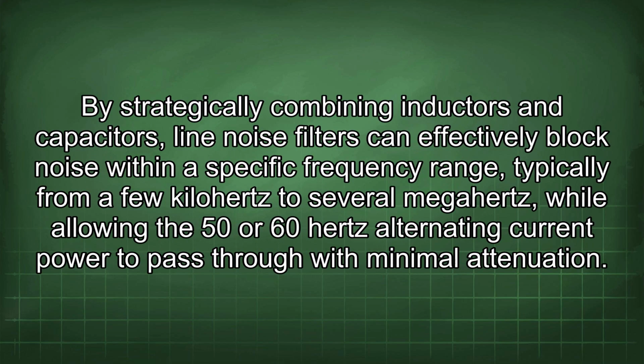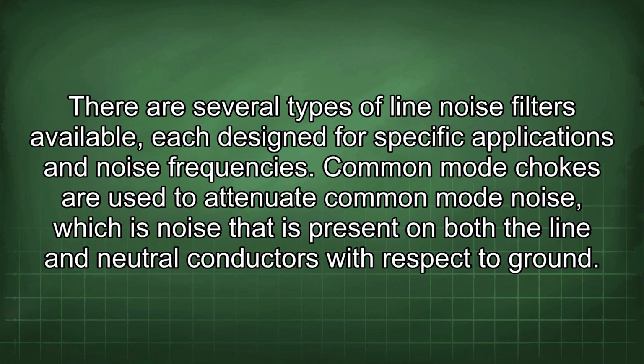By strategically combining inductors and capacitors, line noise filters can effectively block noise within a specific frequency range, typically from a few kilohertz to several megahertz, while allowing the 50 or 60 Hz alternating current power to pass through with minimal attenuation. There are several types of line noise filters available, each designed for specific applications and noise frequencies.